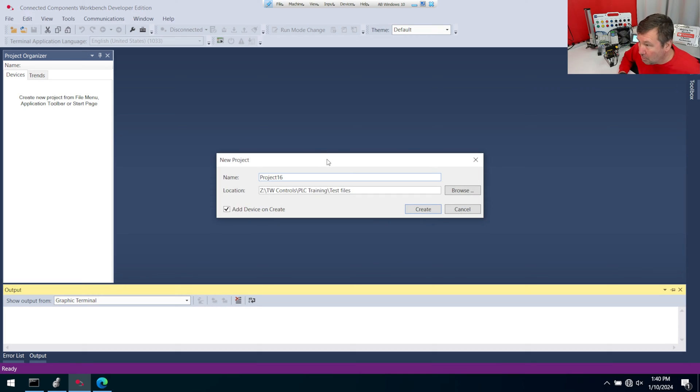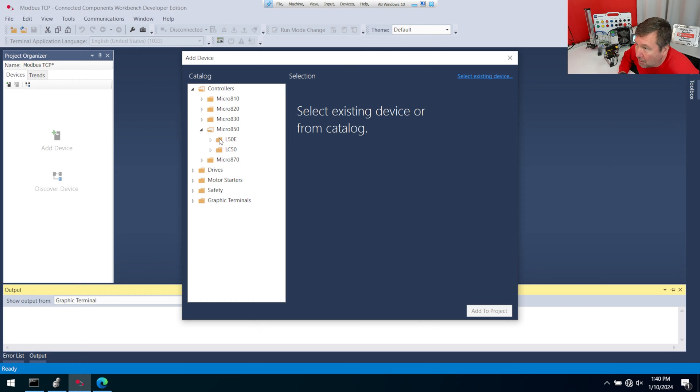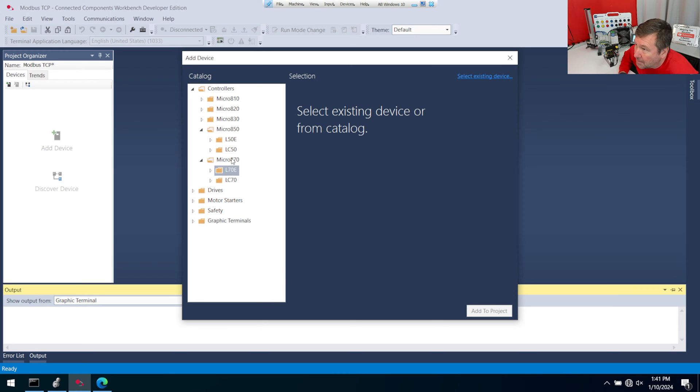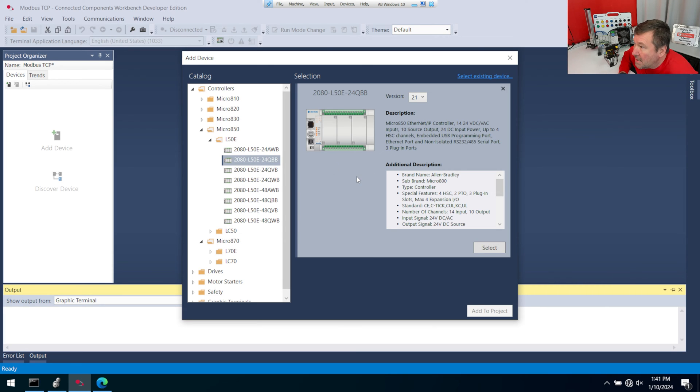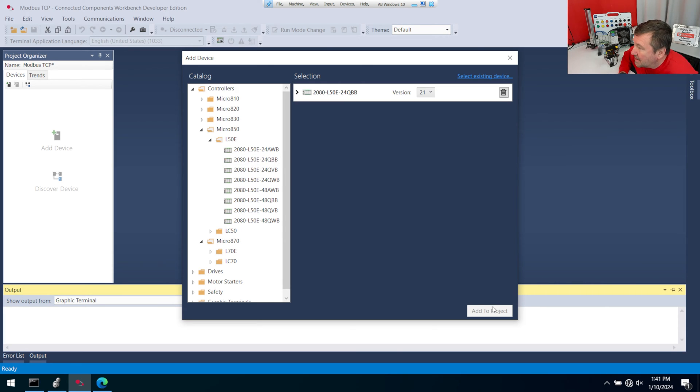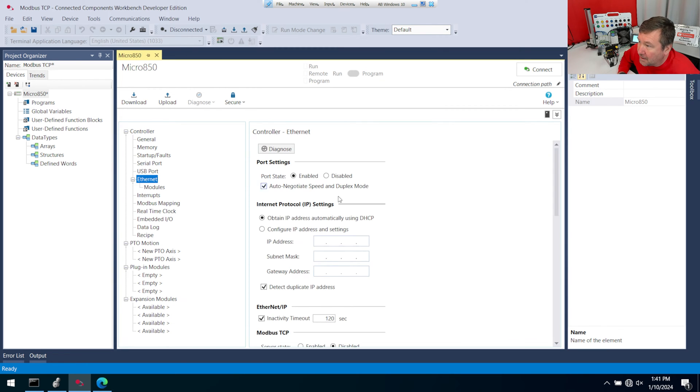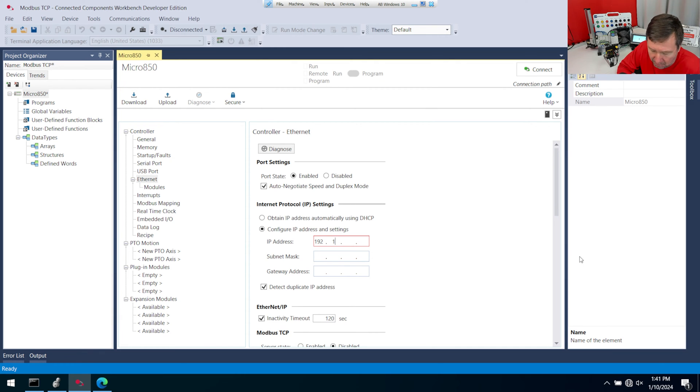We're going to start with a new program. Then we're going to go into controllers, and we have a Micro 850. Just to recap, we did a video on how to use the Ethernet IP Class 1 messaging with the L50E, and that also works with this L70E. But the method I'm showing you today will work with everything from the Micro 820 to the Micro 870. So I am going to grab an L50E, and your trainer has a 2080 L50E 24QBB. Select and add to project. And before we do anything, we're going to click on Ethernet here and set the IP address of our PLC. Because if you download this program without doing this, it reverts back to DHCP.